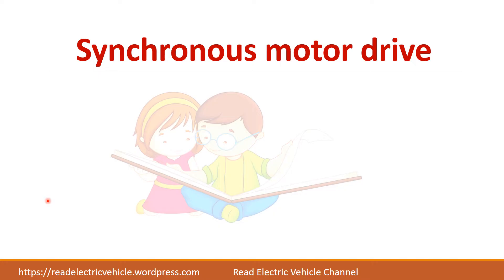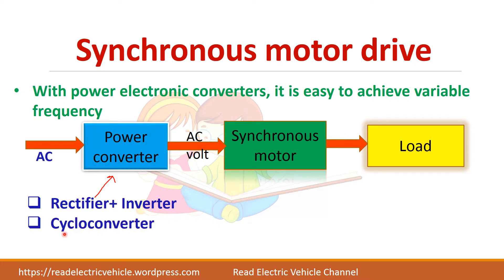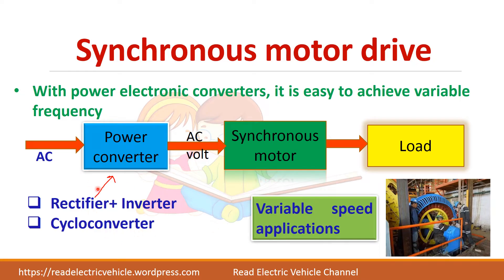The synchronous motor needs an AC voltage, and this input voltage should be variable voltage and variable frequency. We can use a power electronic converter which can convert fixed AC voltage and frequency into variable voltage and frequency. We can use either a rectifier and inverter combination — the rectifier converts AC to controlled DC, which is given as input to the inverter — or we can use a cycloconverter, which is also called a frequency changer, where the input frequency can be different from the output frequency. By using power electronic converters, we can achieve variable speed applications in synchronous motor drives.